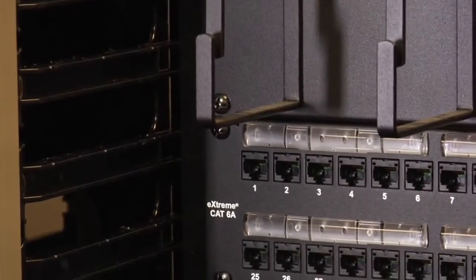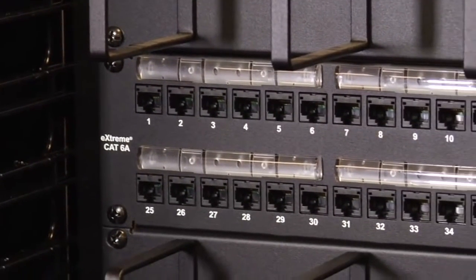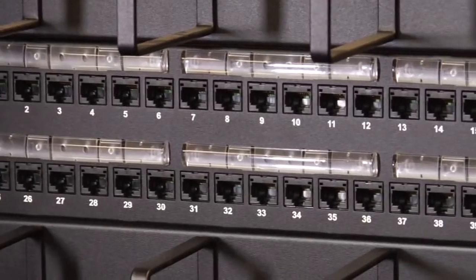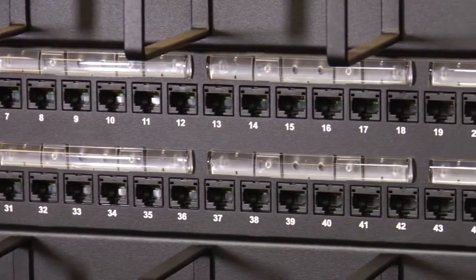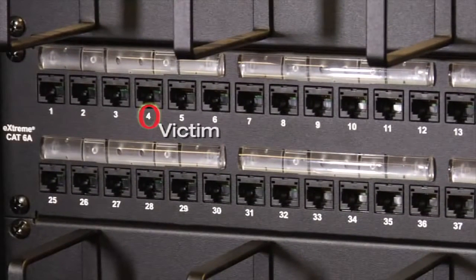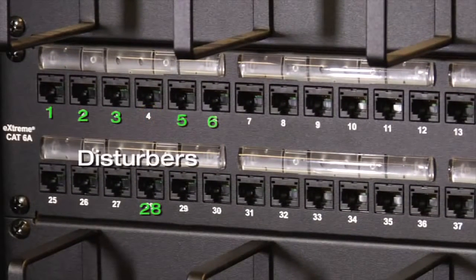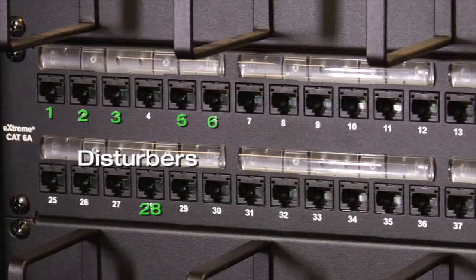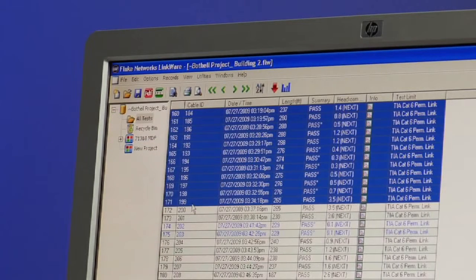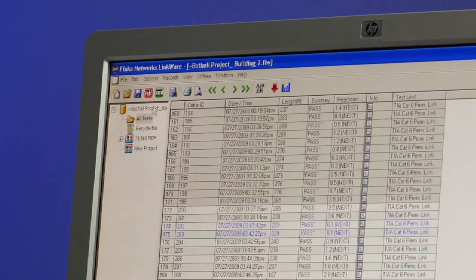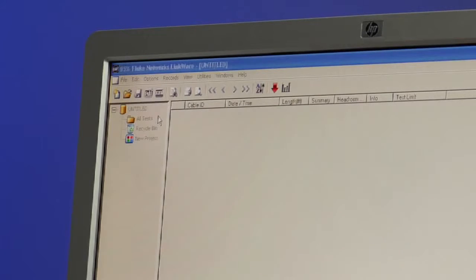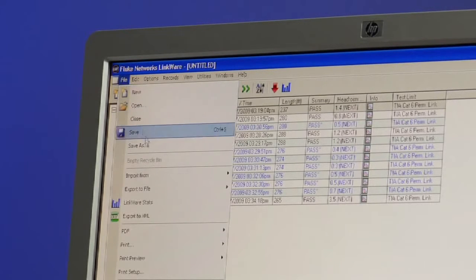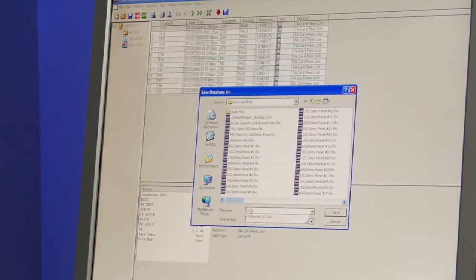Now we need to decide which links to choose as disturber links. We're going to analyze the combined crosstalk interference on a victim link by all its disturber links. Picking the disturber links is easy. These are the links that share the bundle with the victim and any that are terminated in close proximity, usually just above or below the victim link in the panel. Let's look at the linkware database again, this time by link ID. We select all of our disturber links and place them with their corresponding victim links. Now the most difficult part of the job is done. It was actually very easy.